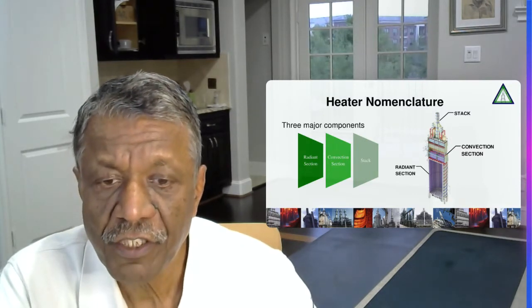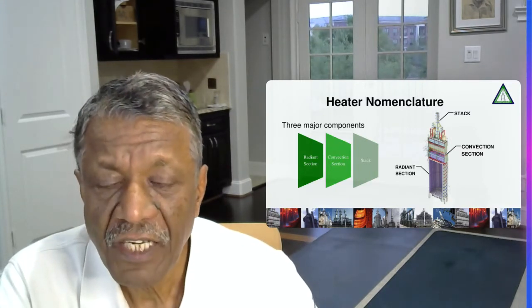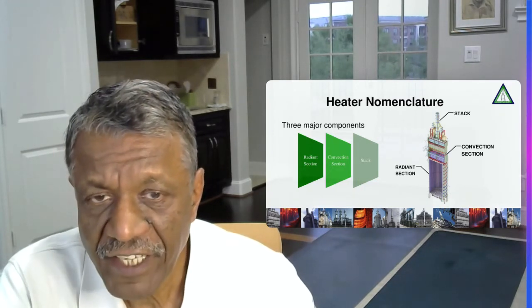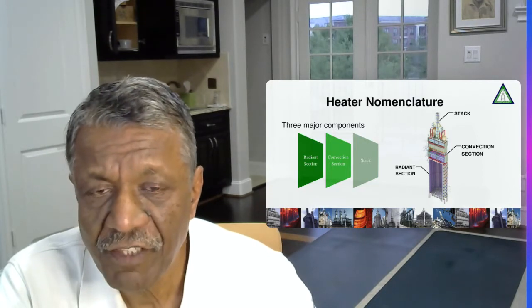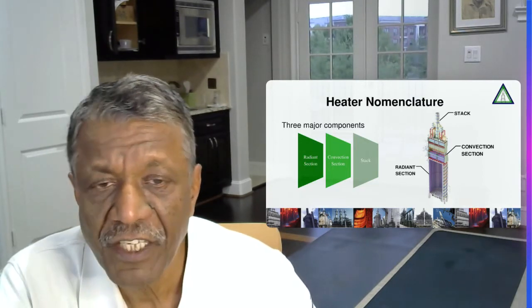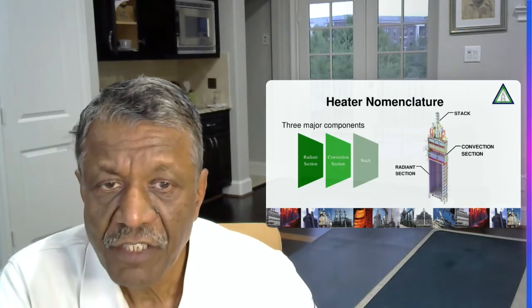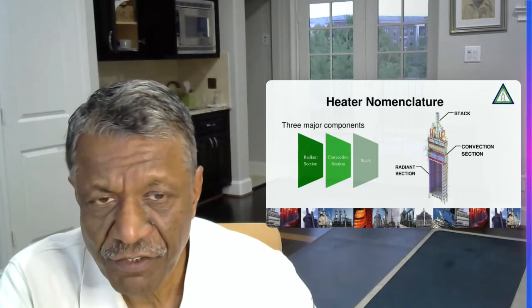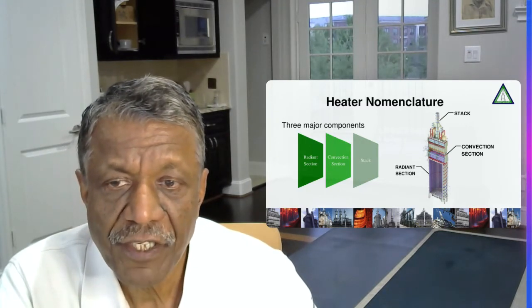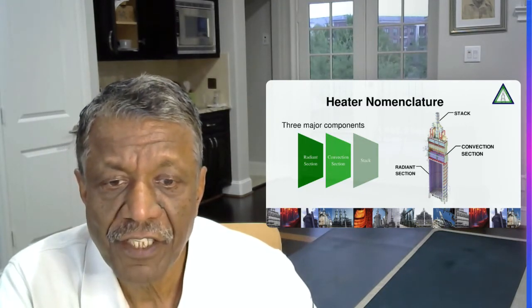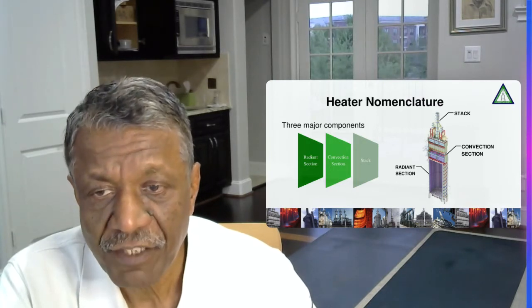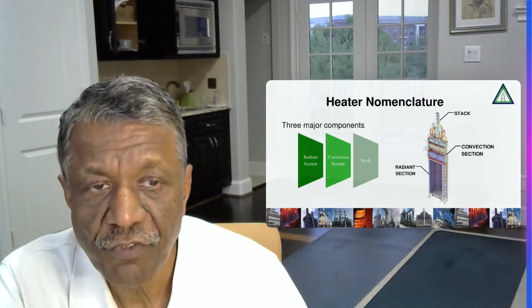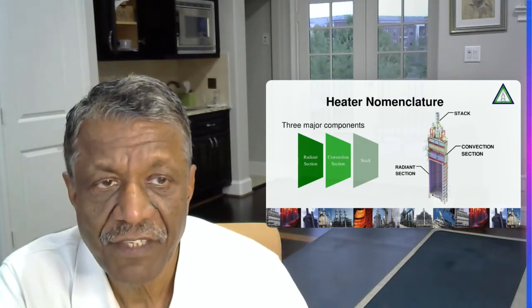So any furnace we are talking about will have three major components. They will have a radiant section where most of the heat, anywhere between 60 to 80 percent of the heat is transferred by radiant section. Then we have convection section where 20 to 40 percent of the heat is transferred in the convection section. And the third component is a stack where the flue gases are disposed safely to the atmosphere. So these are the three major components we are showing over here: a radiant section, convection section and stack.